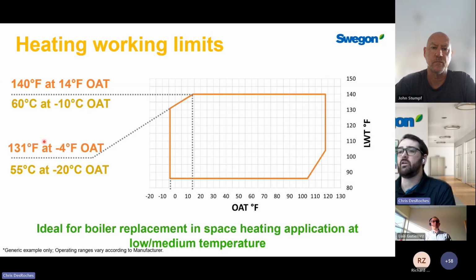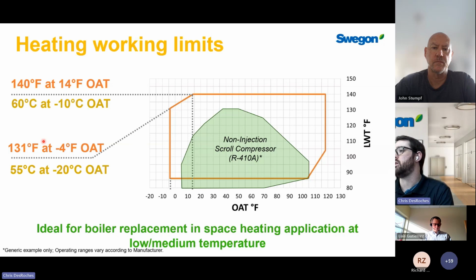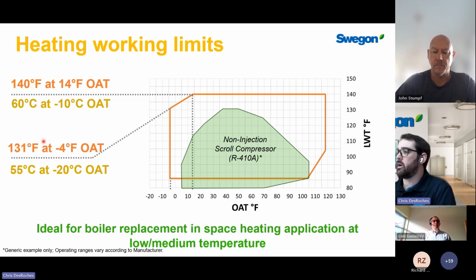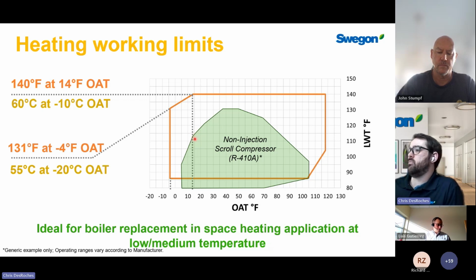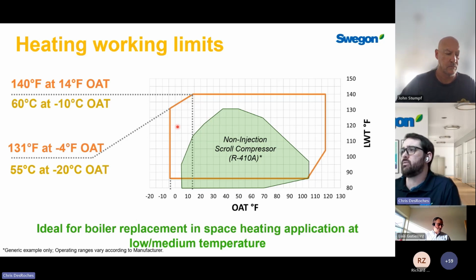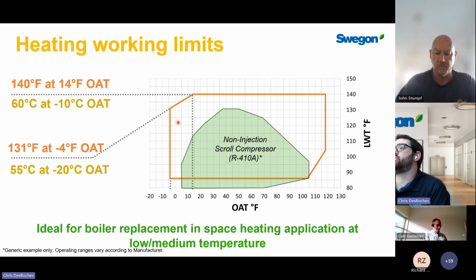So that will drop off, but we still generate 130 water at -4F. So it's really more closely related to typical condensing boiler temperatures that we're used to designing with for hydronic heating systems. And just to put it in perspective and compare the older generation of air source heat pumps that have been on the market, 3 years ago would typically not have injection scroll compressors. So this meant we saw a much more drastic drop off of our supply temperature output from the machine as it gets colder outside. So those types of products we'd see being designed maybe to 14F with 113 water temperature. But with the liquid injection, because we're able to maintain the high lift, we're able to generate much higher water temperatures, and it's more suitable for use in cold climates where we still need high water temperatures at cold ambient conditions.